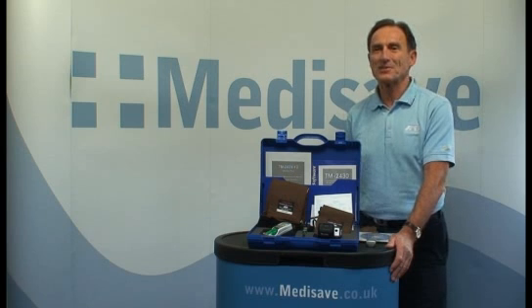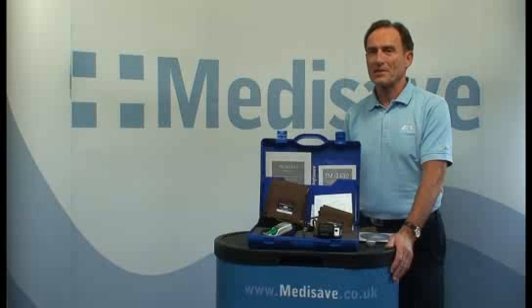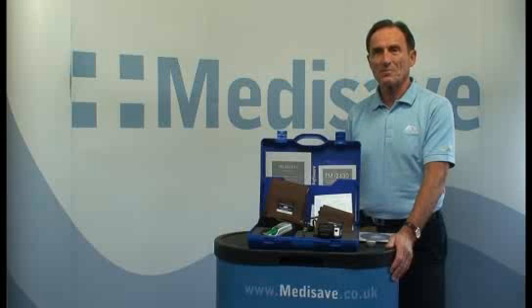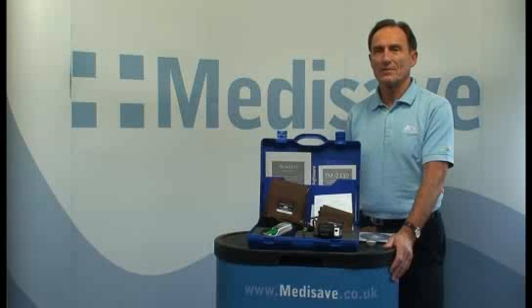Welcome to a short presentation on the TM2430 ambulatory blood pressure monitor from A&D Medical. This unit is clinically validated to British Hypertension Society highest grade A over A, and can be used by GP practices to determine blood pressure readings away from the surgery. This can be invaluable to decide on medication levels and for patients suffering from white coat hypertension and even avoid masked hypertension.